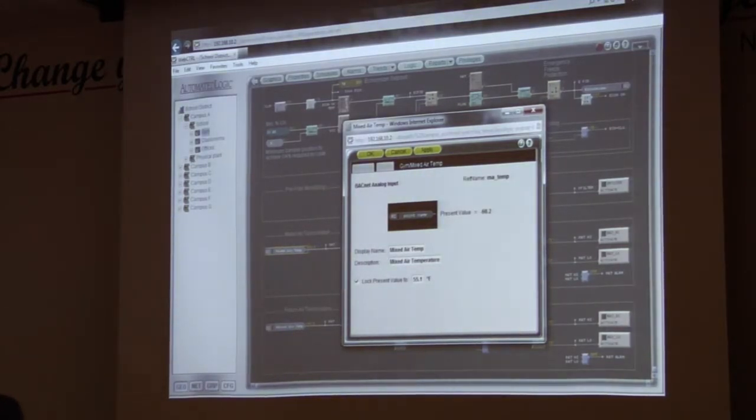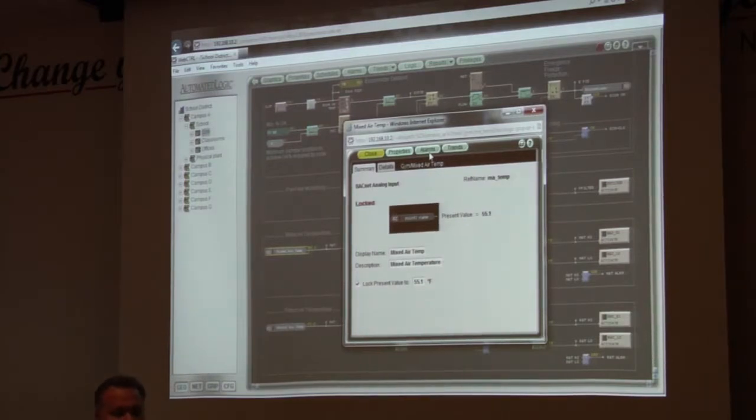For you guys, they put in the apply saying, you know what, if you're locking something, you're probably just doing some troubleshooting, and you're probably going to want to undo it. So it applies it to the system and keeps the window open for you. So if I'm testing something, I could hit it, it'll stay there, right? Because I could get involved in something really quick if I'm on a building, right? And in case I forget to come back, at least someone else will walk in going, hey, who locked this?